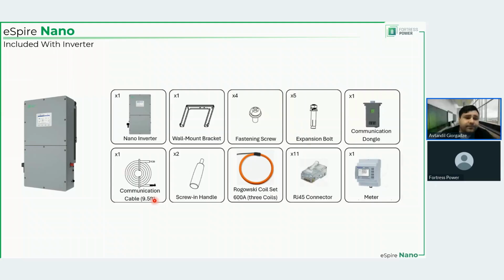Communication cable, obviously, for closed-loop communication between the inverters and between the batteries. Screw-in handles. Those handles are screwed in on the side right here and on the opposite side of the inverter. This allows you to move the inverter around more easily. Technically speaking, once the inverter is affixed to its permanent location, you can remove the screw-in handles. Rogowski coils, 3 of them. They are rated for 600 amps each.